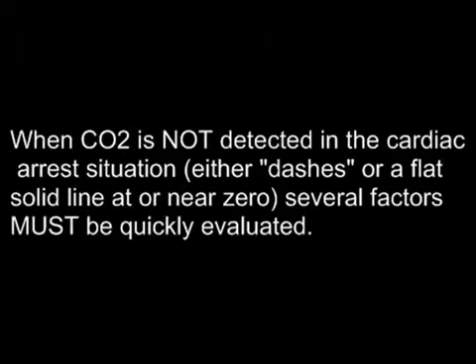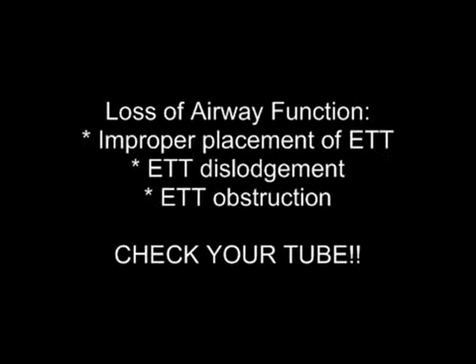When CO2 is not detected in the cardiac arrest situation, either dashes or a flat solid line at or near zero occur, and several factors must be quickly evaluated. Always check the connection at the endotracheal tube and at the LifePak 12 monitor. A shock may have been delivered and the system is resetting — this could take up to 20 seconds. The system may also be auto-zeroing, which could also take up to 20 seconds. Additional causes include loss of airway function, improper placement of the ET tube, ET tube dislodgement, or ET tube obstruction. Always check your tube.